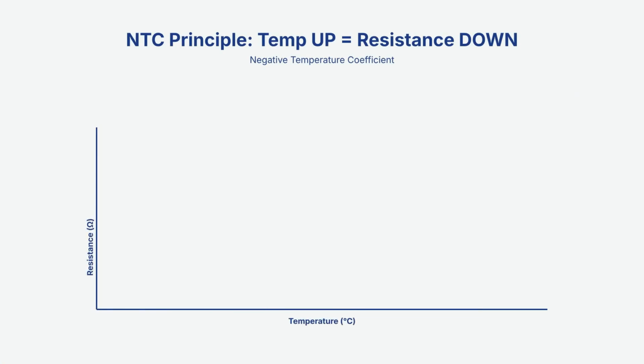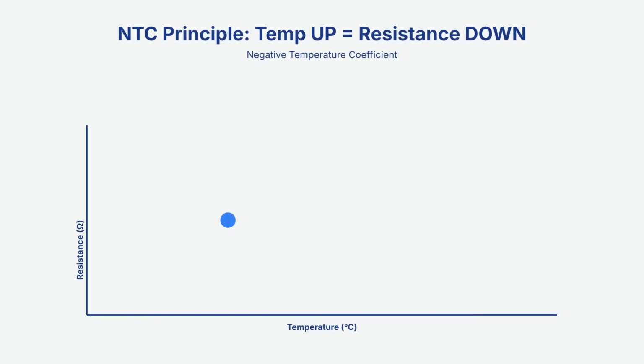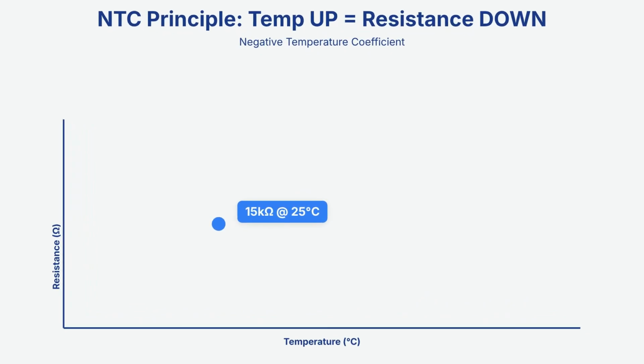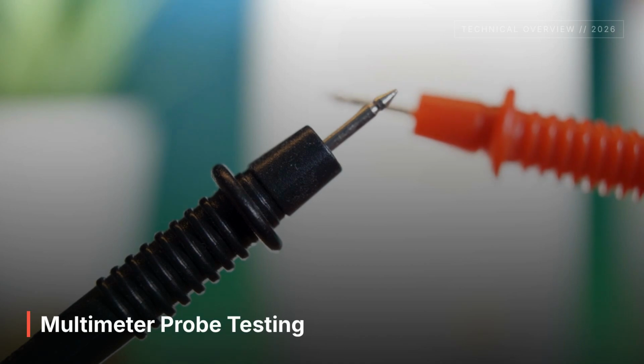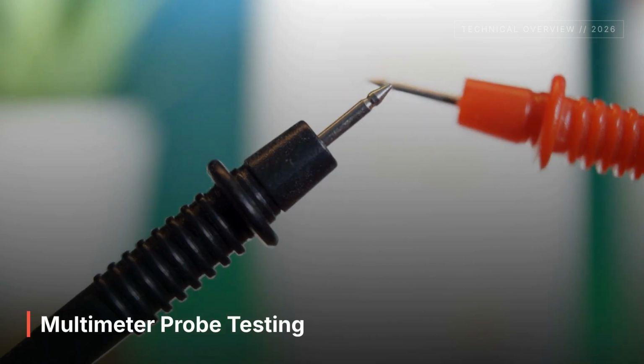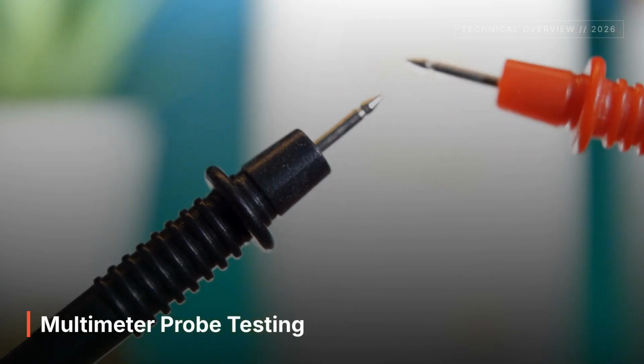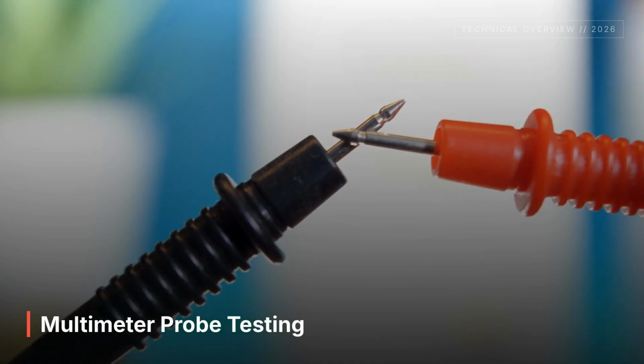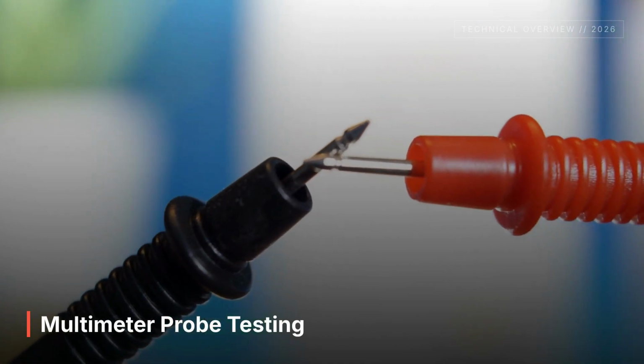Here's where the magic happens. Grab your digital multimeter and turn the dial to resistance, set to the 20K range. Standard Hisense room sensors are typically rated at 15,000 or 10,000 at 25 degrees Celsius. As the temperature goes up, the resistance reading should smoothly drop. Place your red and black probe tips into the tiny pinholes of the white terminal connector. At normal room temperature, we should see roughly 10K to 15K.